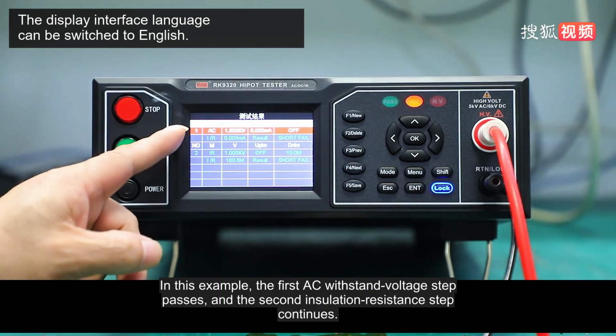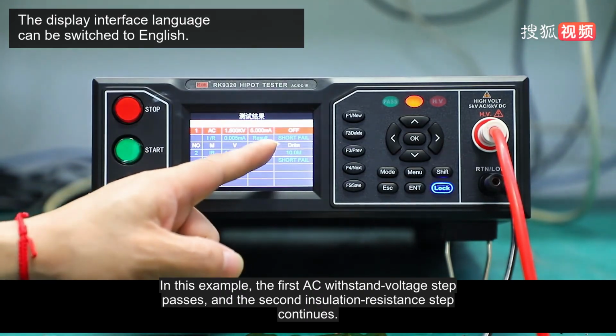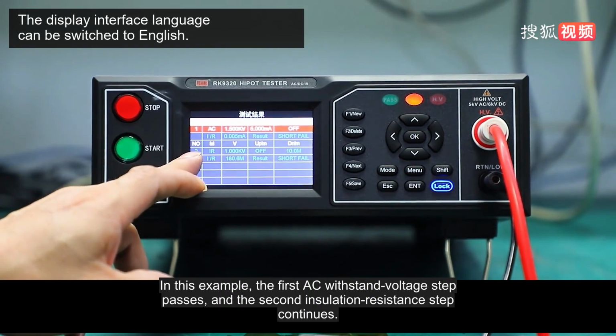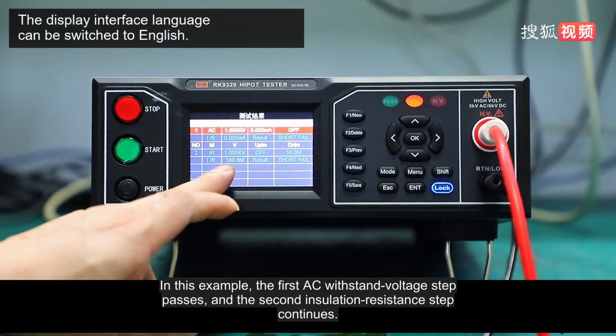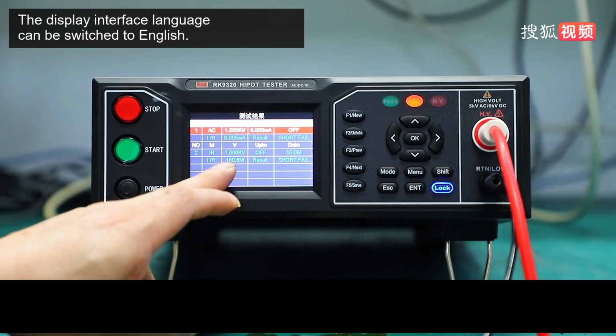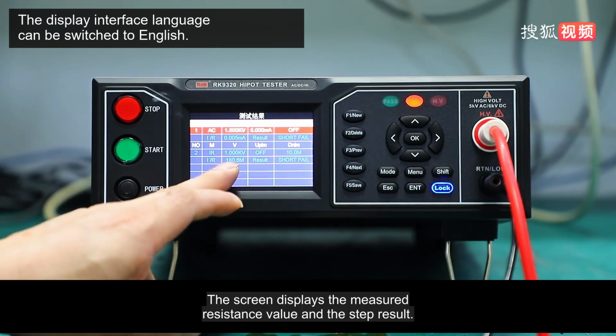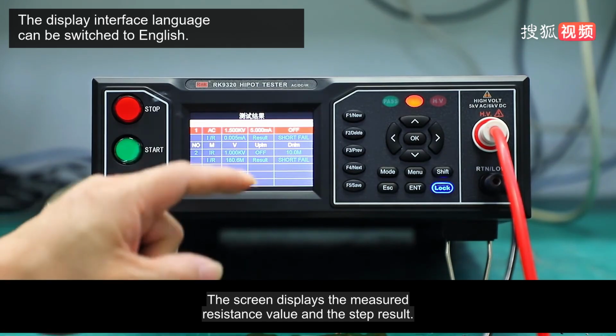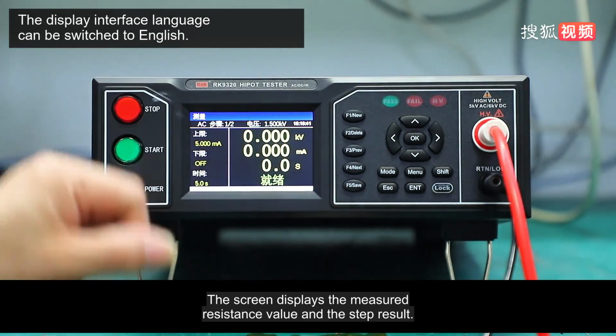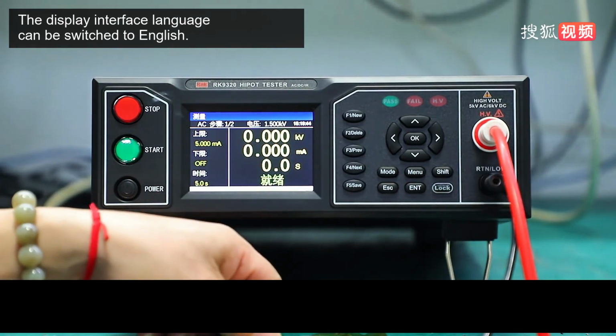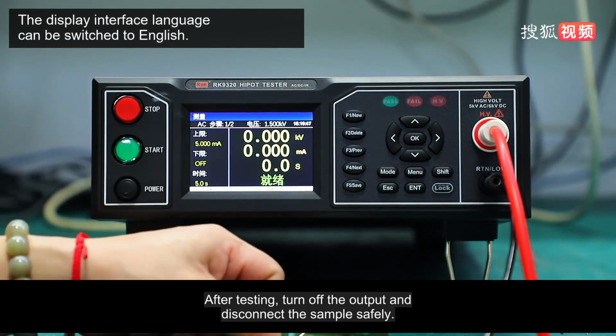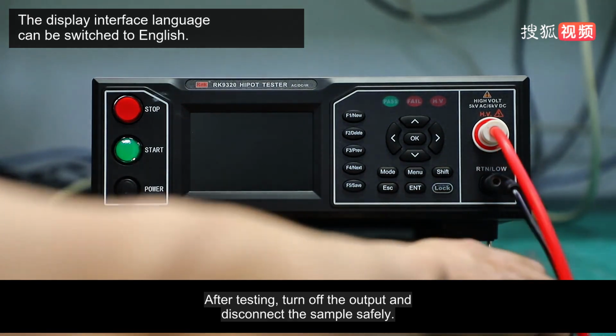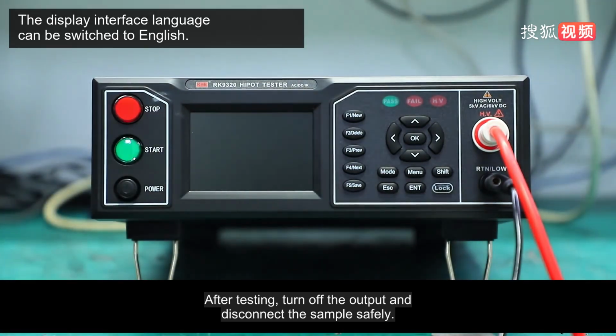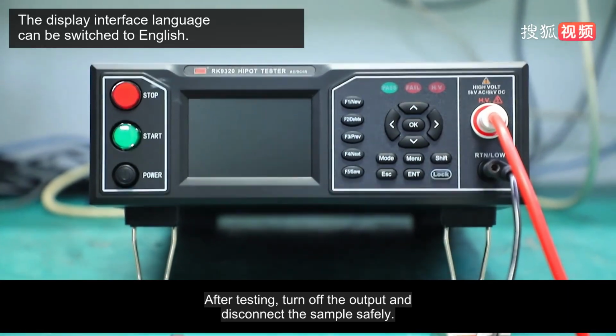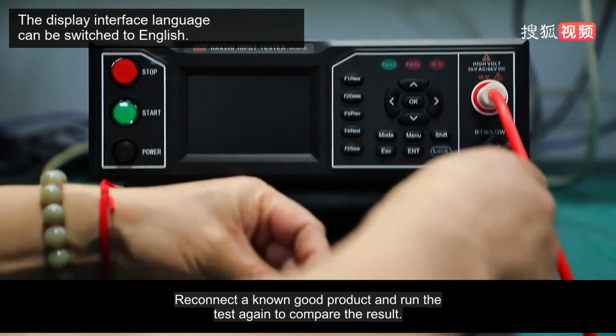In this example, the first AC withstand voltage step passes and the second insulation resistance step continues. The screen displays the measured resistance value and the step result. After testing, turn off the output and disconnect the sample safely. Reconnect a known good product and run the test again to compare the result.